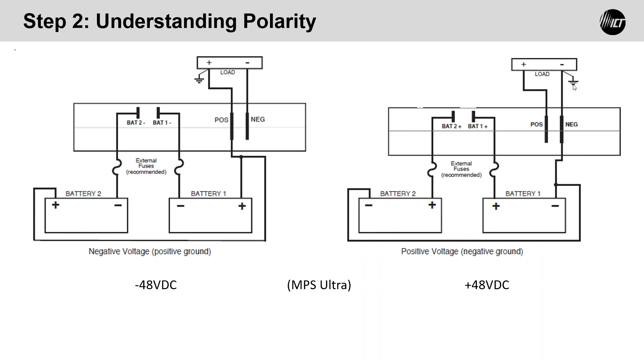The opposite is true if you have a plus 48 system. The plus side of the battery — battery 1 plus and battery 2 plus — are the two strings, and the positive terminal is carrying the load, while the return is the negative, referenced to ground here. So we have positive voltage, negative ground in this particular configuration.